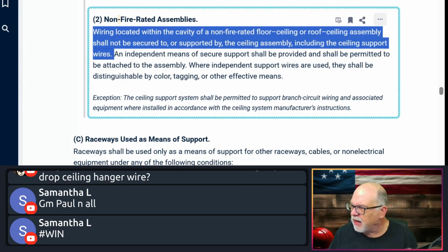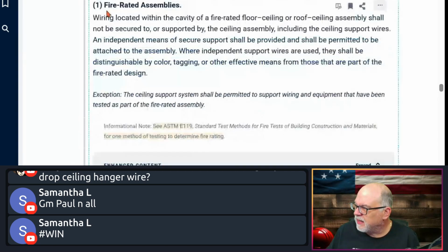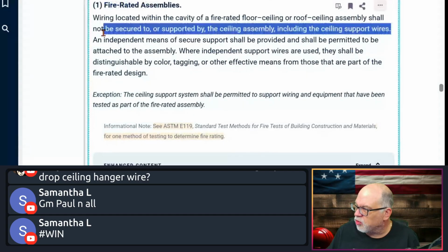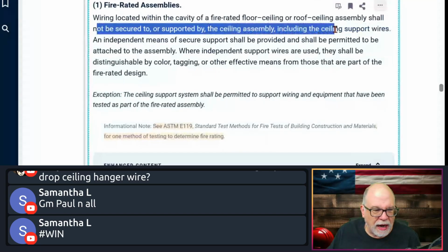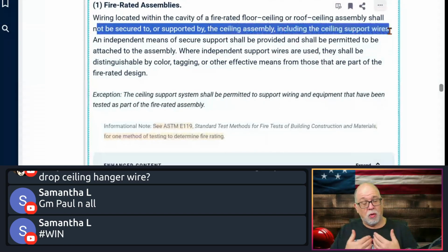Okay. And just to say the same thing here for the fire rated assembly, it says exactly the same thing right here. Not secured to or supported by the ceiling assembly, including the ceiling support wires. So if you're running MC, which is germane to our topic, you're going to run your own wires, not the ones that are designed to support the ceiling. That type of thing.